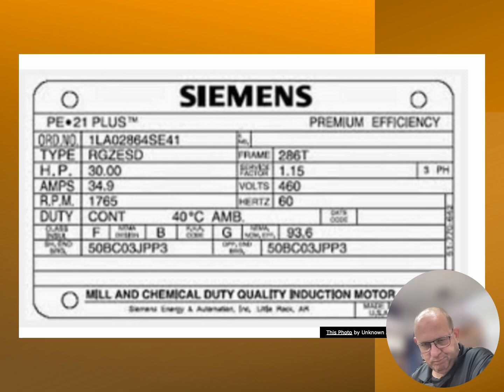I have a unit that does not have a minimum or maximum breaker on this particular unit. So what do I do in this case where I have a motor that I'm trying to wire up on this particular unit? I would use the NEC, okay, and it gives you the corrective factor for the max amp draw for that unit. The nameplate only gives you the amp draw on it. So what you're going to end up doing is you're going to take the amp draw of that unit and you're going to multiply it by 1.25.